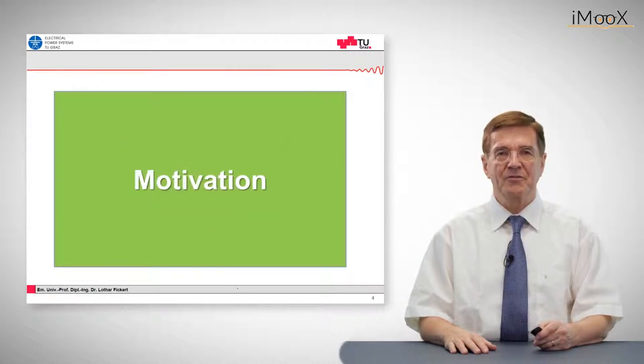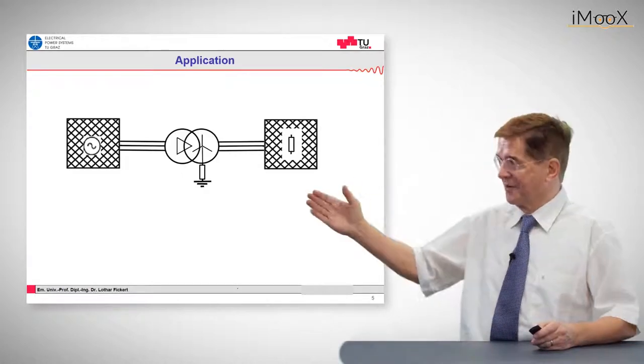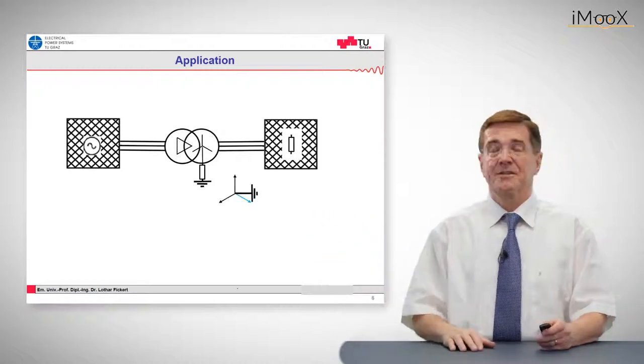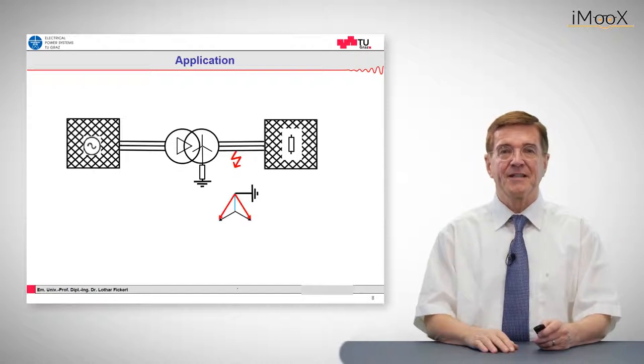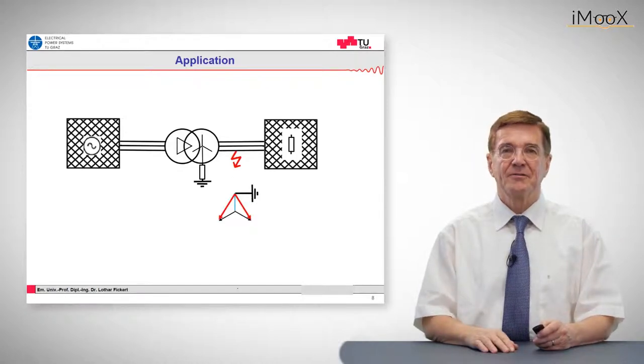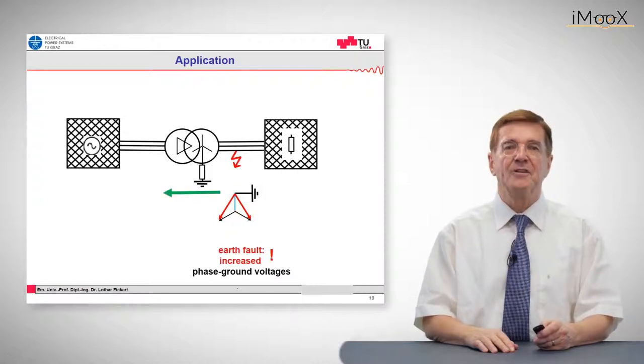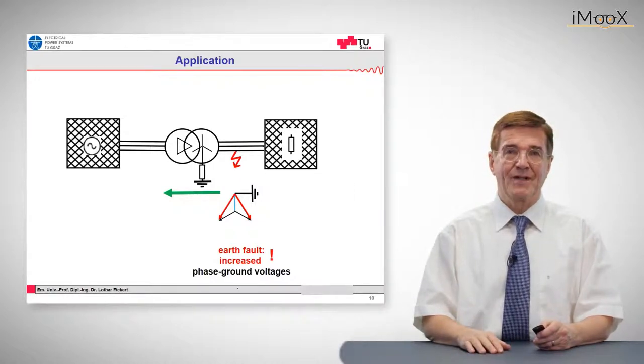These transformer vector groups are motivated by the fact that earth faults on one side of the system, in this case on the right side, which change the voltage from regular voltage into elevated voltages on the secondary side, should not be transferred to the primary side.